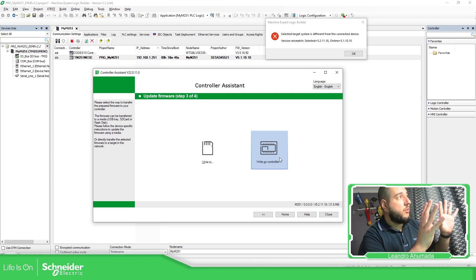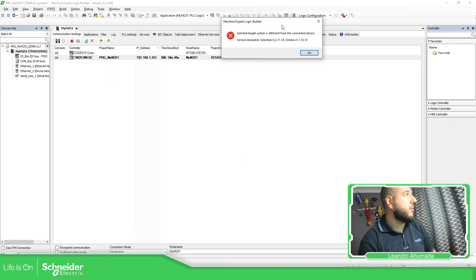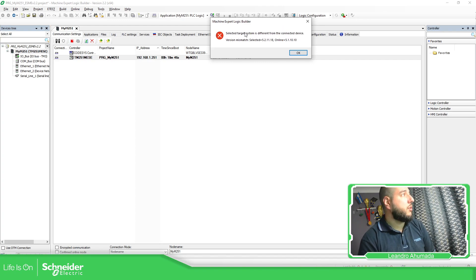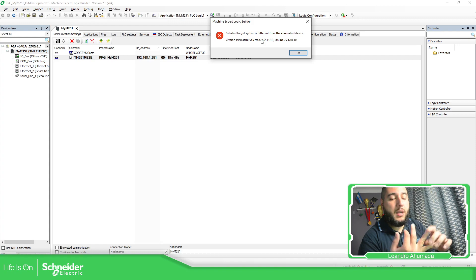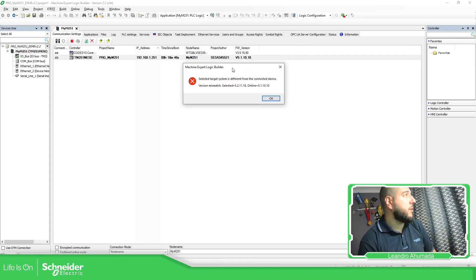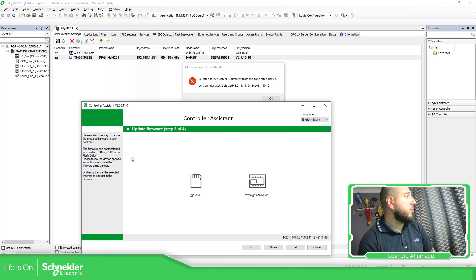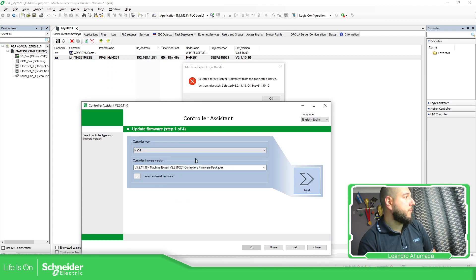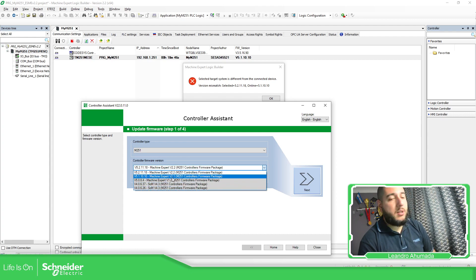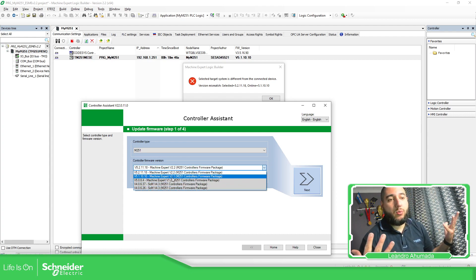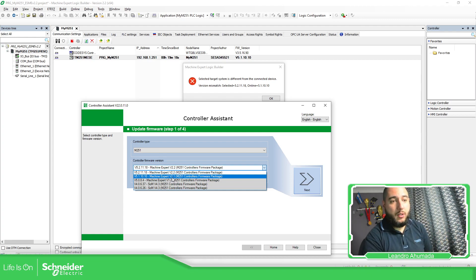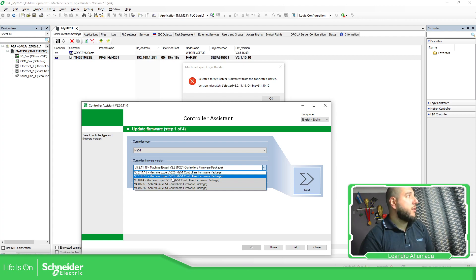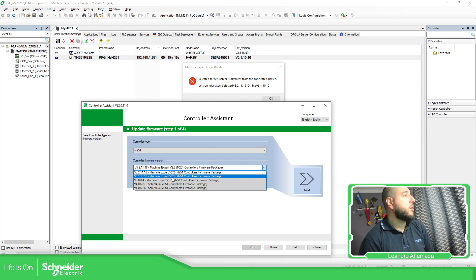So this is the issue that we have. If you have this selected target system is different from the connected device version mismatch, just need to check which is the software that you're using right now, and which is the firmware. The firmware can be checked over here. And in order to check which is the firmware that you need to use, just go back home. In case you don't know, here you have the possibility to select which one is the one that you have. But basically, you just need to change the firmware of the M251 if you want to download your project. If you have a different one, then you just need to find the right version of the software in order for you to connect.